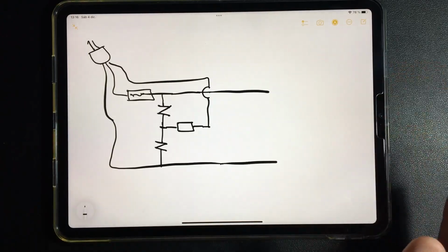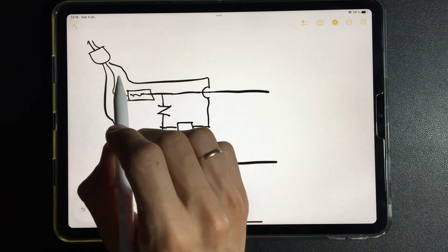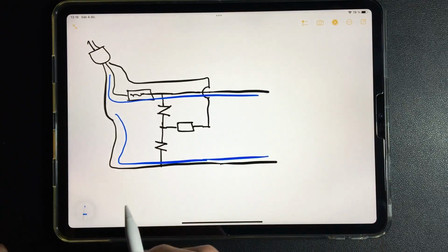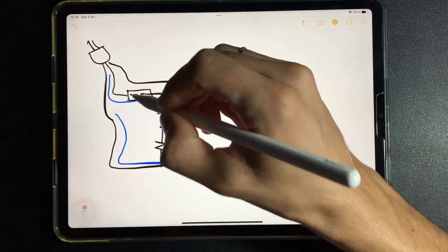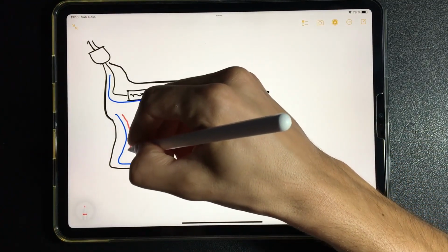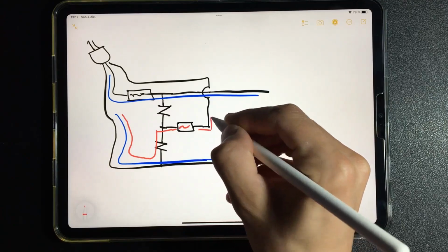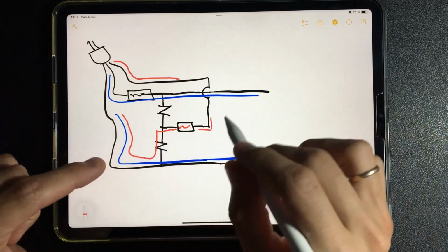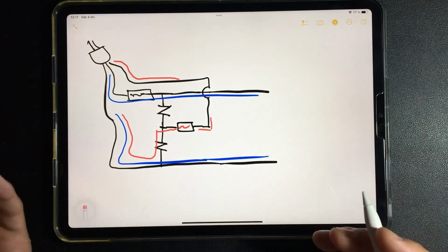Here the circuit continues and everything else, but what is the purpose of this? If we have normal voltage positive and negative, they continue their path and feed the equipment. But if we have excess voltage, it will be diverted through one of the two varistors. We will jump this fuse, we will cross it, and we will go through the ground wire, and the circuit breaker will trip. The circuit breaker will trip and de-energize the equipment, thanks to this circuit. This protects it against high voltage. The system is good, well done.